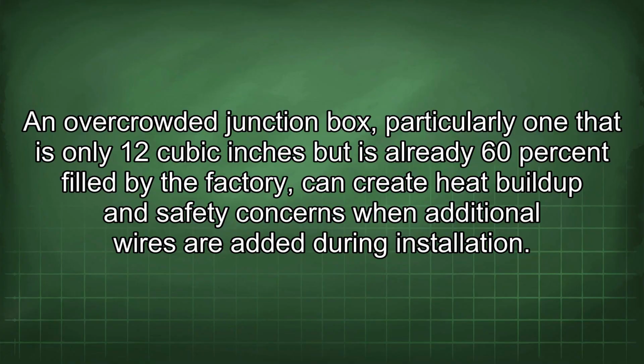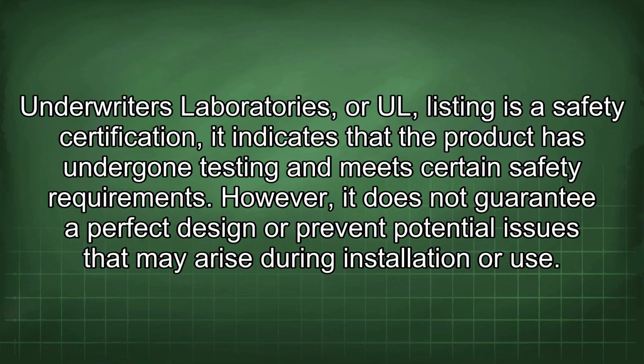An overcrowded junction box, particularly one that is only 12 cubic inches but is already 60% filled by the factory, can create heat buildup and safety concerns when additional wires are added during installation. Underwriters Laboratories, or UL listing, is a safety certification. It indicates that the product has undergone testing and meets certain safety requirements. However, it does not guarantee a perfect design or prevent potential issues that may arise during installation or use.